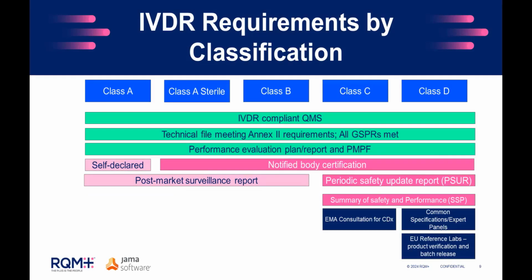The requirements are pretty consistent across classes with a few differences as you have lower risk and higher risk devices. But for all devices, you must have that compliant QMS system. You must have a tech file meeting Annex 2 requirements, and you must meet all of the GSPRs. And you must have a performance evaluation plan and report and PMPF plan. For Class A devices, you're self-declared, so you don't have to worry about notified body requirements, but all other devices from Class A sterile up to Class D require a notified body assessment and certification.